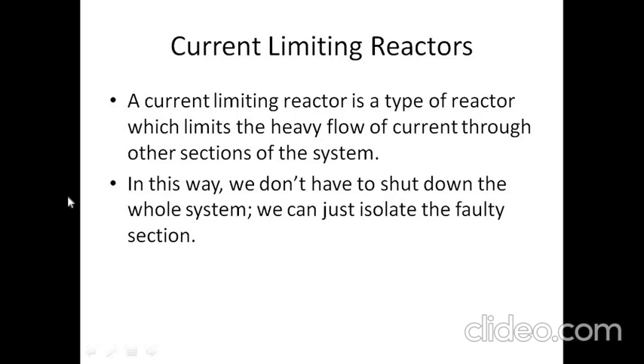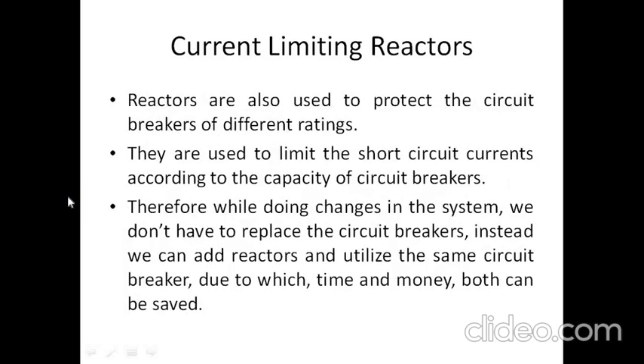In this way we don't have to shut down the whole system — we can just isolate the faulty section from the healthy section with the help of this reactor system. Reactors are also used to protect circuit breakers of different ratings. If the fault current magnitude is very large, this reactor is also used to protect the circuit breakers. They limit short circuit currents according to the capacity of the circuit breakers, so while doing changes in the system we don't have to replace the circuit breaker.